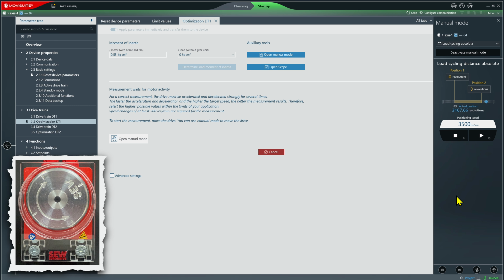I need to go over here and click this gear control, and that will open some extra hidden controls, and I need to reference my drive. If you don't know what that means, don't worry about it. We'll learn more about that later. So I click this, and the brake briefly releases, and the motor is now referenced. I'm going to set my acceleration slider to maximum because when you tune the drive, you want to produce a measurable jerk, and you can do that by setting the acceleration to a fairly high value.